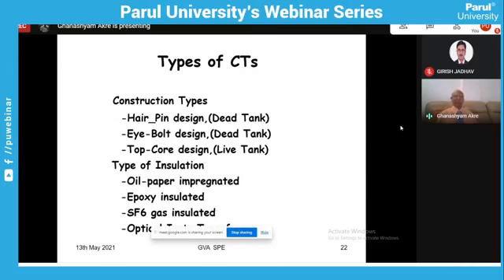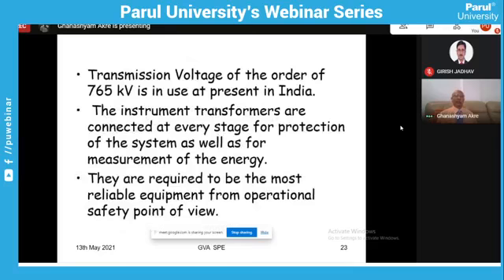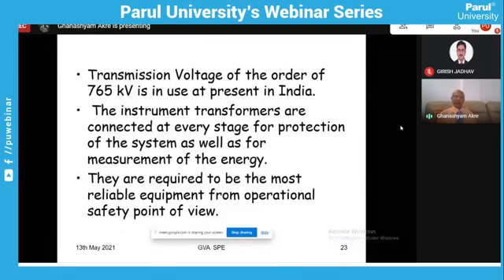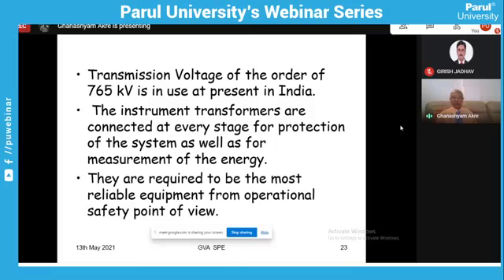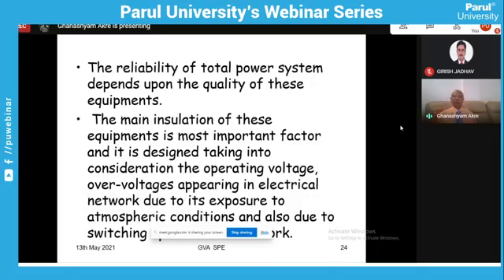So let us go for the details of this. I already explained that the instruments are connected at every stage of the protection of the system as well as for the measurement of energy. They are required to be the most reliable equipment from an operational point of view. The reliability of the total power system depends upon the quality of this equipment. The main insulation, that is the isolation between the primary and secondary of this equipment, is the most important factor, and it is designed taking into consideration the operating voltage and the over voltages appearing in the electrical network due to its exposure to atmospheric conditions, and also due to the switching of equipment in the system.